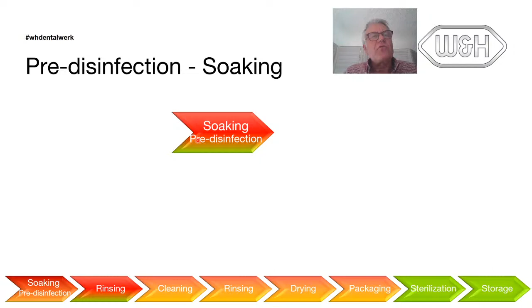This is quite urgent. All the instruments, used and non-used, I repeat myself, must be plunged inside a solution. I'm not talking about the handpieces, okay? You cannot soak handpieces, you must wipe them off. This is one of the limitations and headaches with handpieces, you cannot soak them. Why is it so urgent? Actually, the first purpose is to prevent debris, blood, saliva, or any remains from drying. If you let it dry during lunchtime after saying bye-bye to the patient, it's going to be dry, and believe me, it's very quick. I mean, blood can dry within 10, 15, 20 minutes. It's very fast. If you let it dry, it will be difficult to clean afterwards.